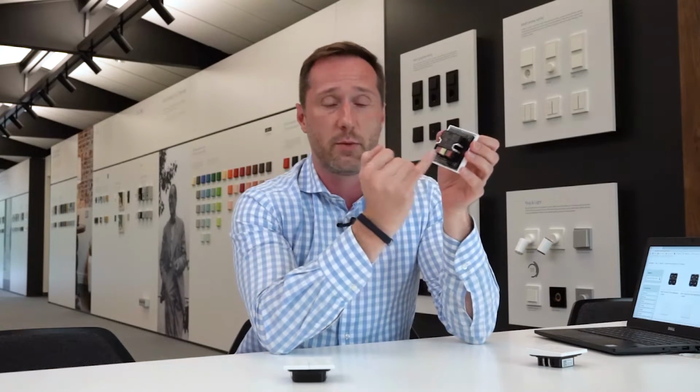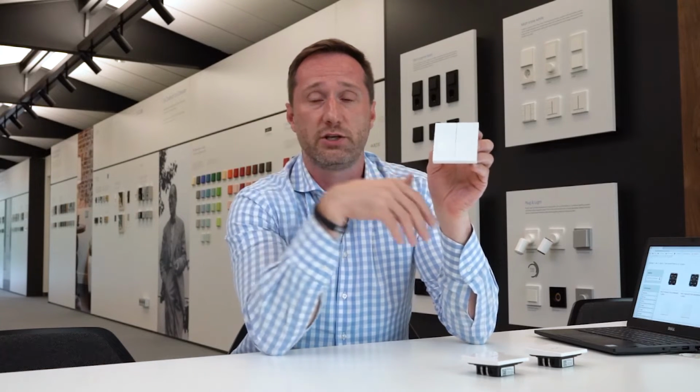Next we have the universal version of our F10 push button. In this case it's a 1-gang rocker type. The main difference is on the back, where you can see that we have additional terminals. These terminals are used to connect either external reed contacts, normal push buttons, or, and then we come to the third device, our extension module for the F10 version. This is a non-KNX participant. It will be connected via the universal push button to the KNX, and then you have a quite cost-efficient version if you need an additional switching point within your project.